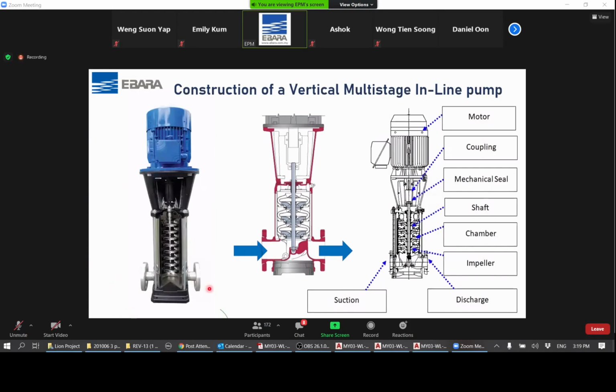Now, the vertical multistage inline pump is one of the most popular types of pump used in a building. And this pump has many good design features and is an excellent choice for water transfer as well as pressure boosting to toilets and fittings. Now, as you can see from the name, it is what we call a multi-stage design. That means it's made up of not only one single impeller but many stages with an impeller in each stage.